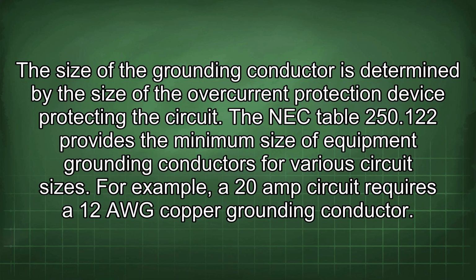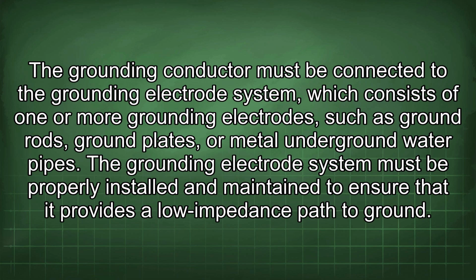The NEC Table 250.122 provides the minimum size of equipment grounding conductors for various circuit sizes. For example, a 20 amp circuit requires a 12 AWG copper grounding conductor. The grounding conductor must be connected to the grounding electrode system, which consists of one or more grounding electrodes such as ground rods, ground plates, or metal underground water pipes.